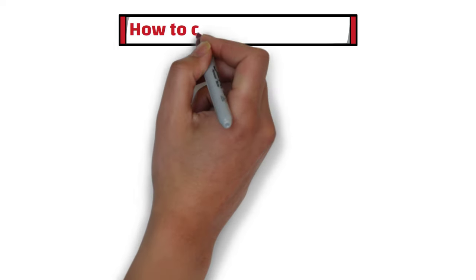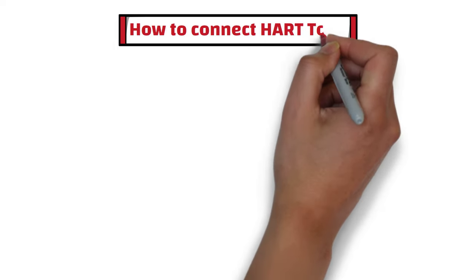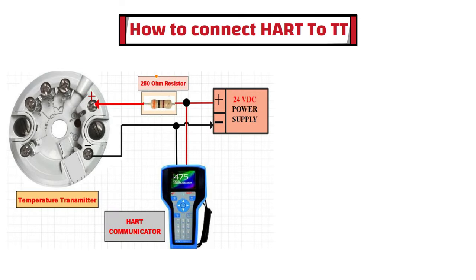First of all, let's learn how to connect the HART Communicator to the temperature transmitter. Connect a 24-volt DC power supply to the temperature transmitter, and also connect a 250-ohm resistor in series with the positive side of the power supply. Connect the HART Communicator between the temperature transmitter and the 24-volt DC power supply as shown in this diagram.